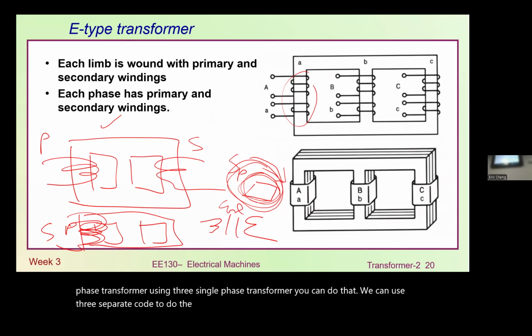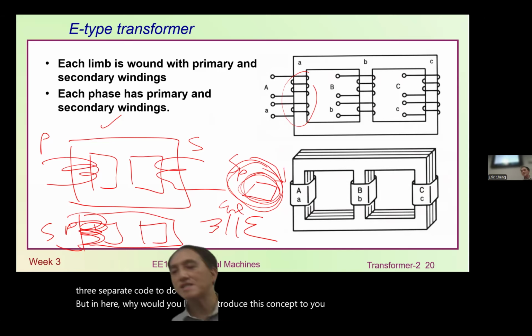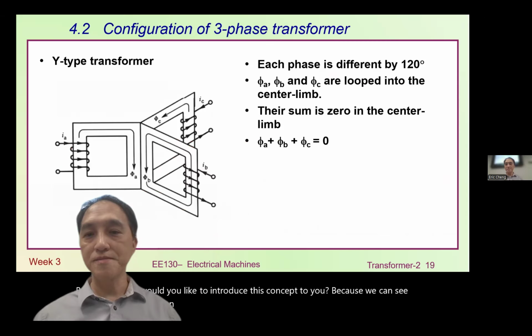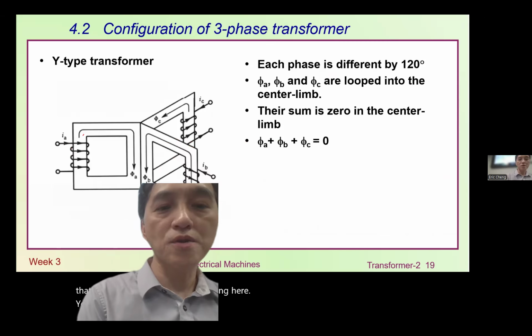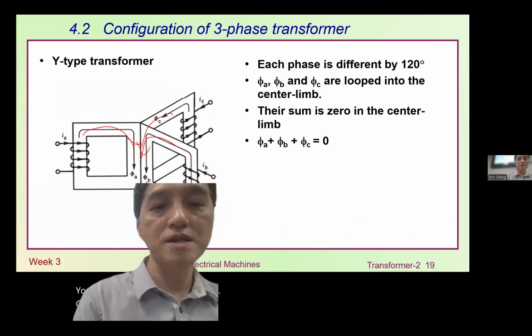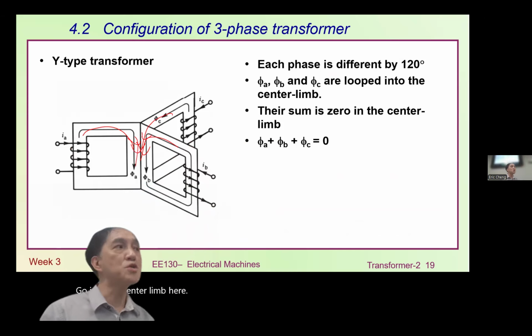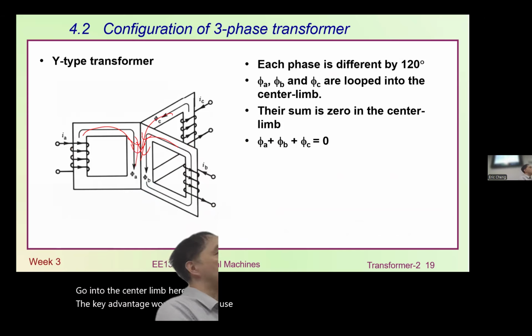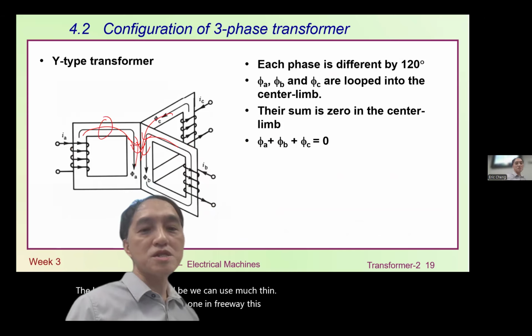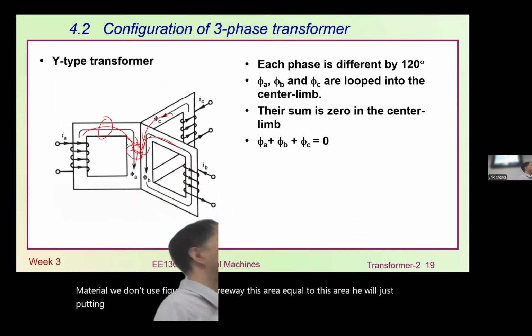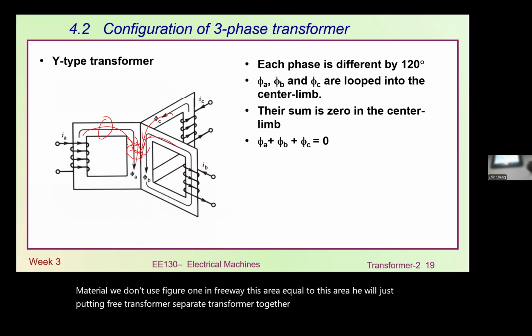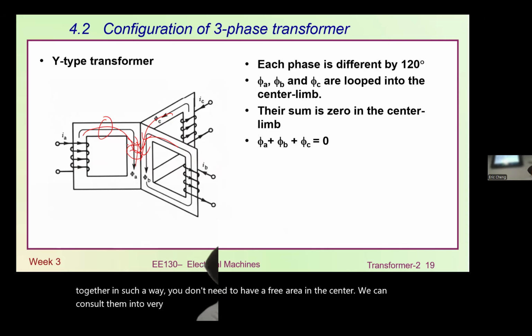But here, why we like to introduce this concept to you is because we get cancellation of flux. You see when the flux goes into the center limb here, the key advantage is we can use much thinner center limb magnetic material instead of a thicker one. In theory, this area equals this area if you just put 3 separate transformers together. But when you join them together this way, you don't need a free area in the center. We can consolidate into a thinner magnetic limb because there is no magnetic flux there, since it all cancels out anyway.